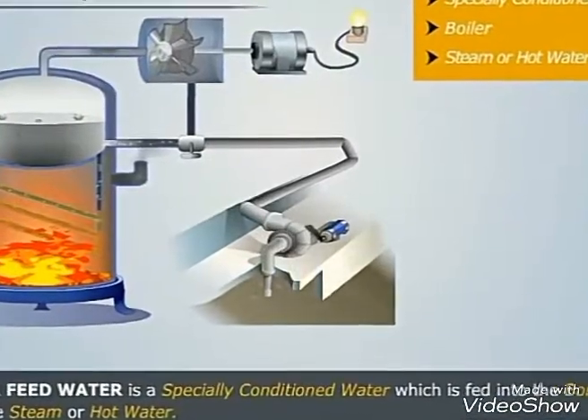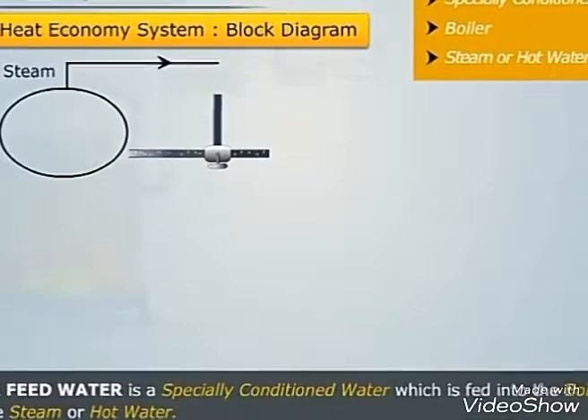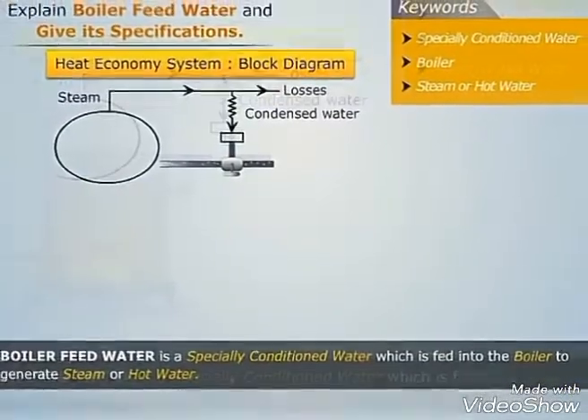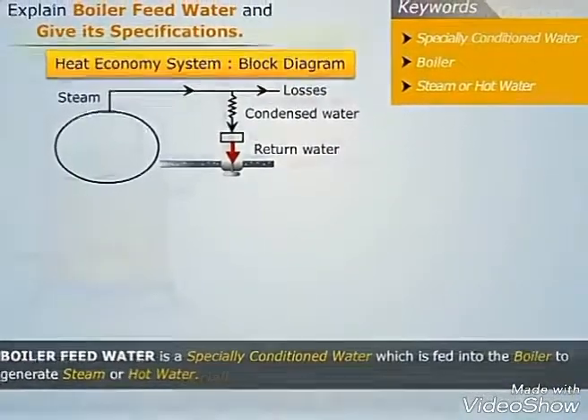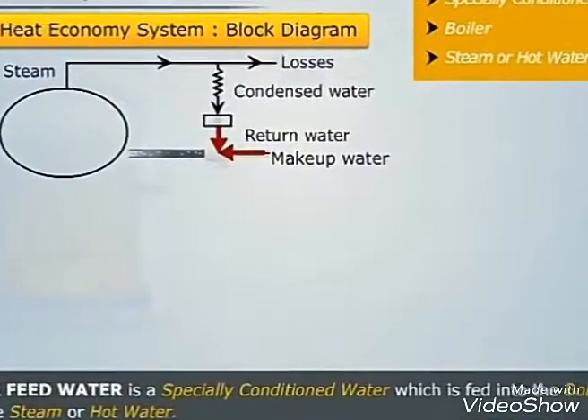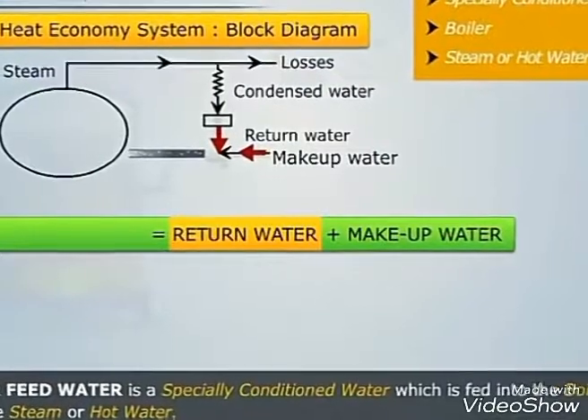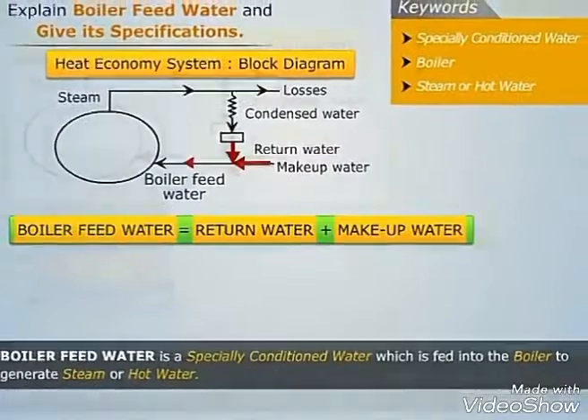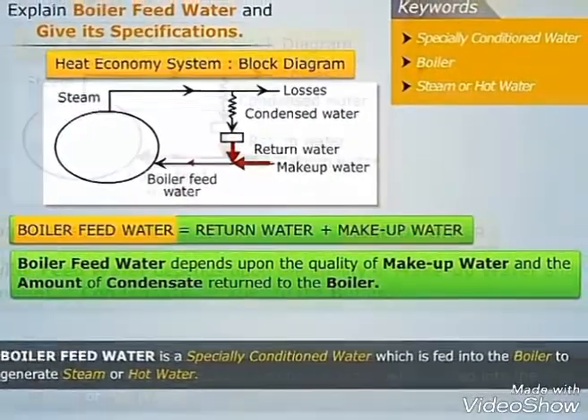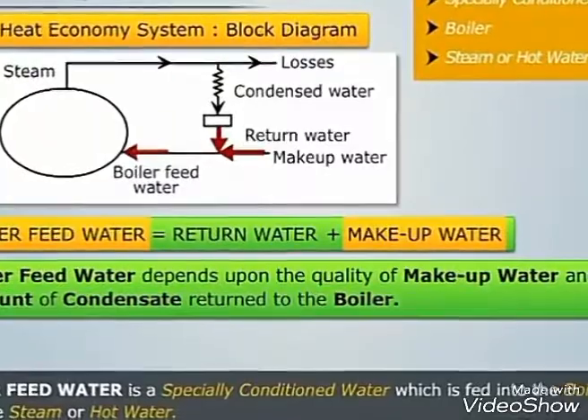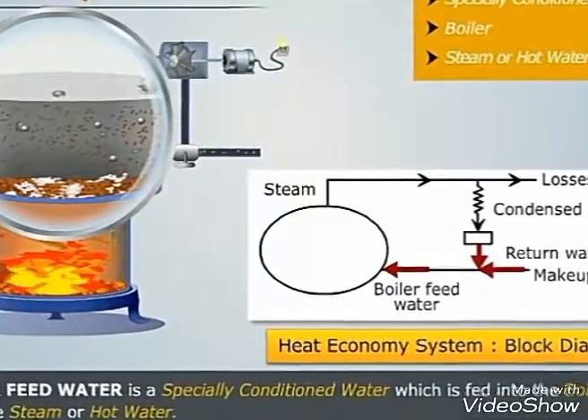Thus, we can say that boiler feed water is specially conditioned water which is fed into the boiler to generate steam or hot water. It is generated through a system of heat economy. Steam produced in the boiler is condensed after use and is returned as pure feed water called the return water. Then some fresh water or make-up water is added to this return water. It is this combination of return water and make-up water which is fed into the boiler as the boiler feed water to generate steam. Note that boiler feed water depends upon the quality of the make-up water and the amount of condensate returned to the boiler.